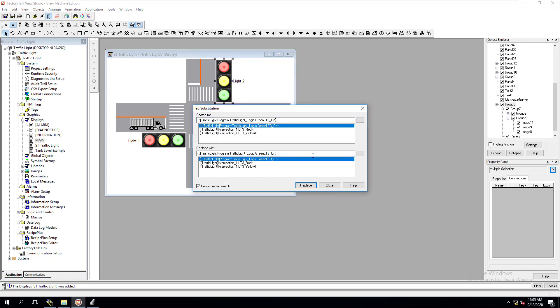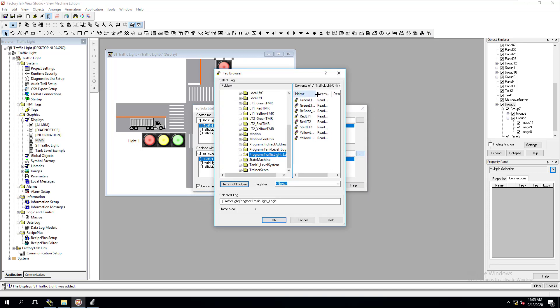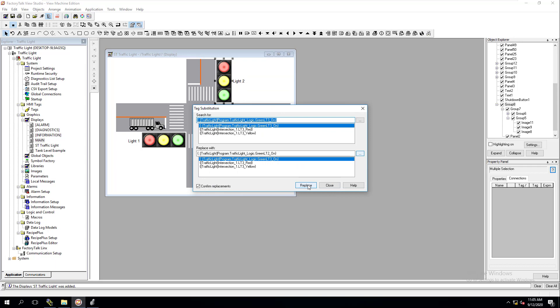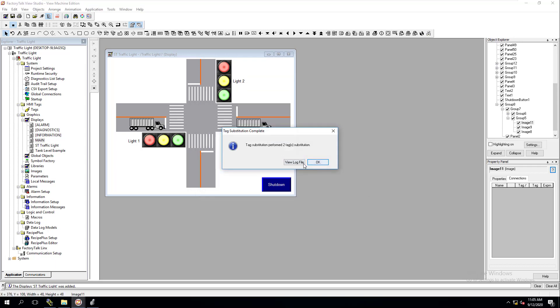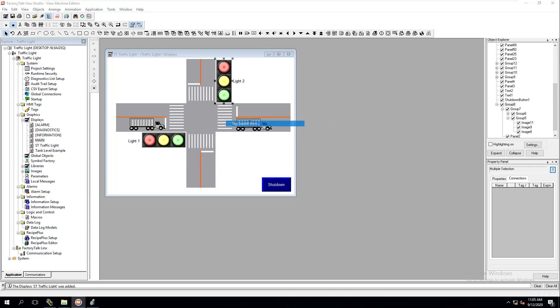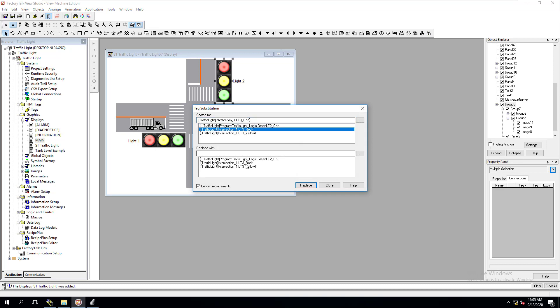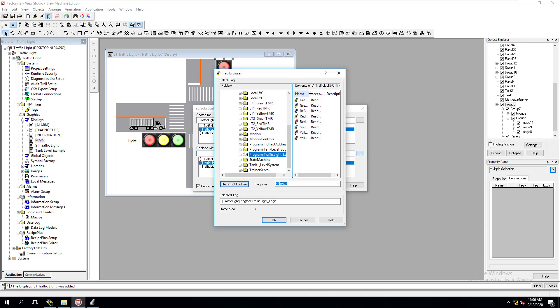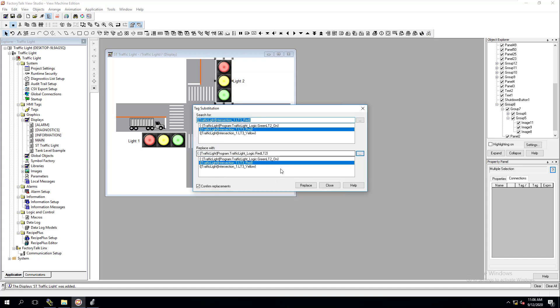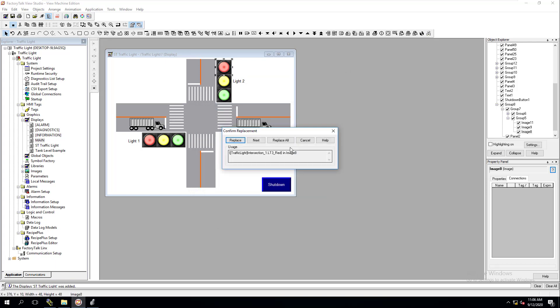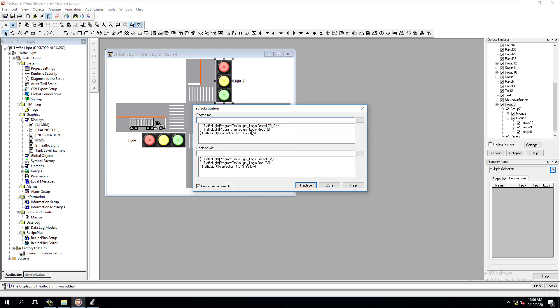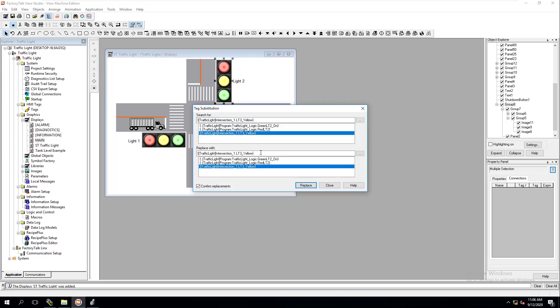We know we don't have a light three, so what we're going to do is come in here and change this back to light two and then replace it. So we have that done. I just wanted to quickly explain that because there's often a misconception that people think you can't just change part of the tag. You can change part of the tag, and there's a much simpler way if your tag structure is really close — you can change that and have it line up perfectly. It saves you a tremendous amount of time.